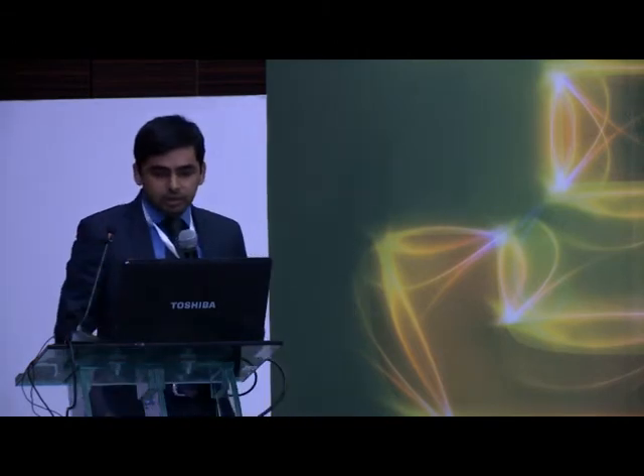fire. Similarly, failure of pressure contacts in the electrical system may be the cause of electrical fire. The arcing and the short circuit will be later stage phenomena, but the root causes will lie either in the design, installation, or preventive maintenance.